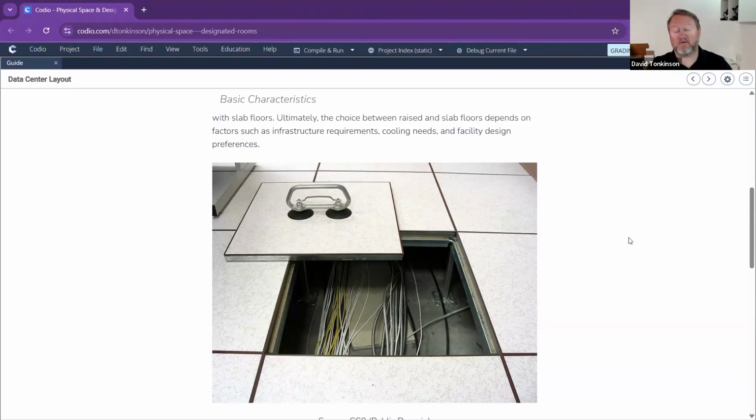Or they can be shifted around and the slots can be changed depending on how the air conditioning is working in that particular area. Remember, we said there are thermometers and temperature checks within your data center area. So if something is running a little bit cooler than it should be, you can probably just put a solid one across the top of it, and that might well keep that one a bit warmer and push the air to somewhere else where it needs a bit more cooling.